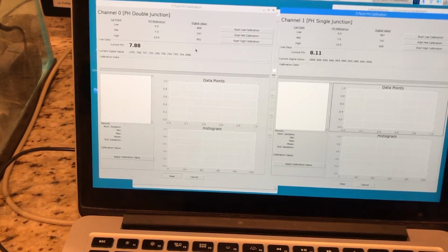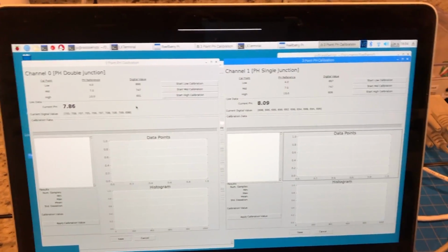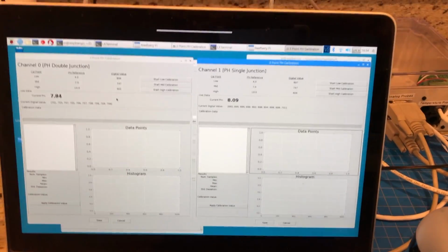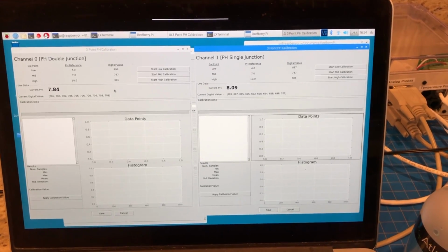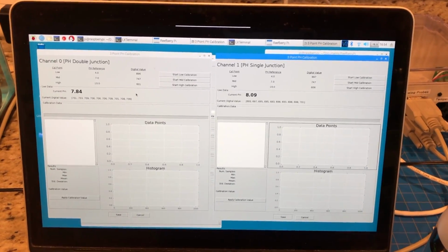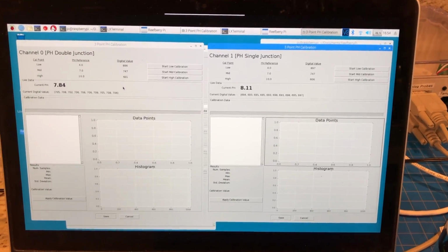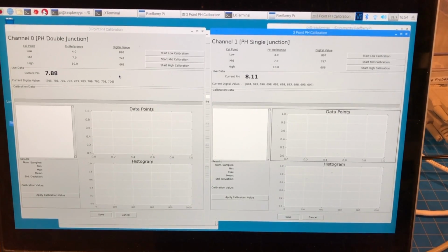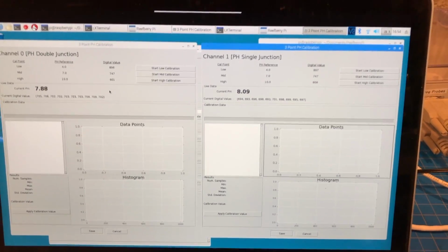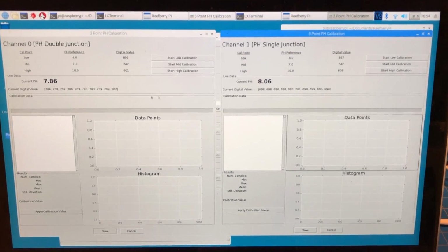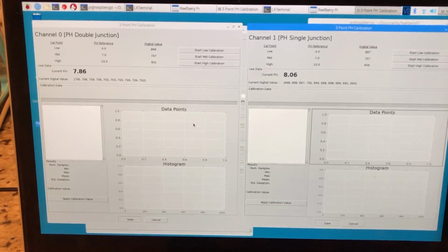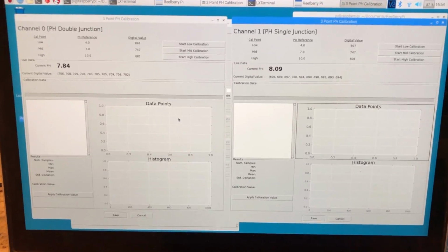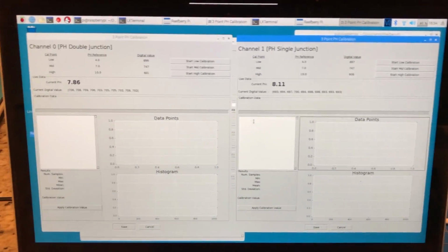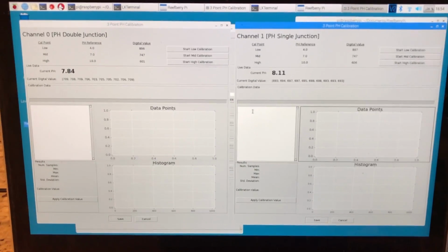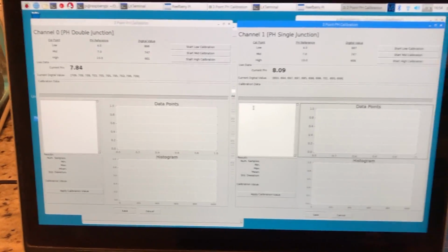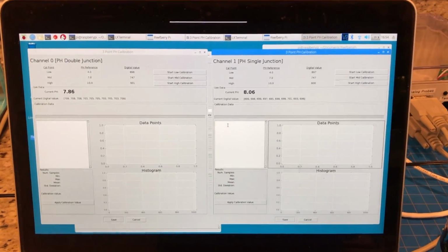I have calibrated these probes, and I will do it again just to verify. But yeah, still something not right there. I just think that those 2 probes do not follow the same characteristic curve, maybe. They have different tolerances. I'm not sure. I can't really find any technical data on those probes, so I really don't know what their stated accuracy or tolerance is. But they're pretty darn close, to be honest. As I get to the calibration points, they are spot on. So there's something a little bit off in the way that they're behaving. I've checked the calculation several times and I think I'm doing everything right, so I need to work on this a little bit more. But let me get the probes in the reference solution, and we'll take a look at it there.